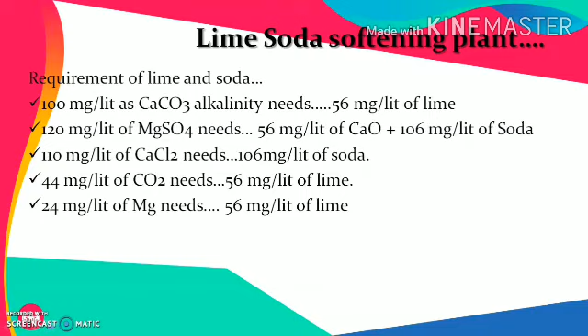In case of carbon dioxide, 44 mg per liter of carbon dioxide needs 56 mg per liter of lime. While in case of 24 mg per liter of Mg, it needs 56 mg per liter of lime or CaO. These are the rules which are used to estimate the total amount of lime soda required at a certain plant to reduce the hardness.